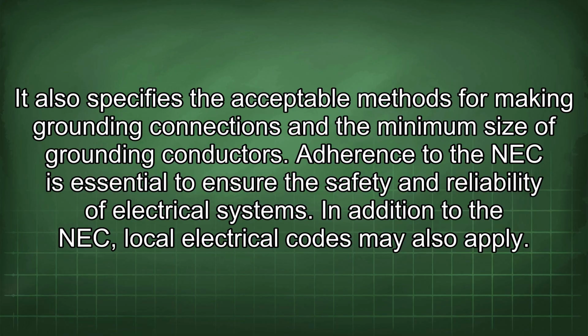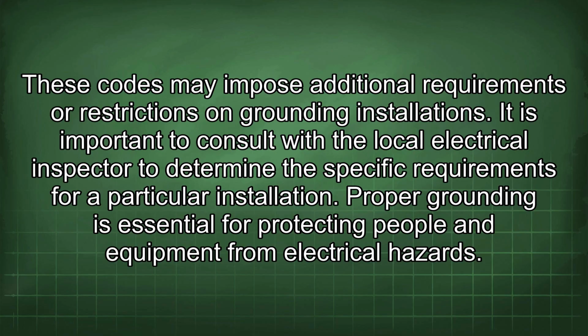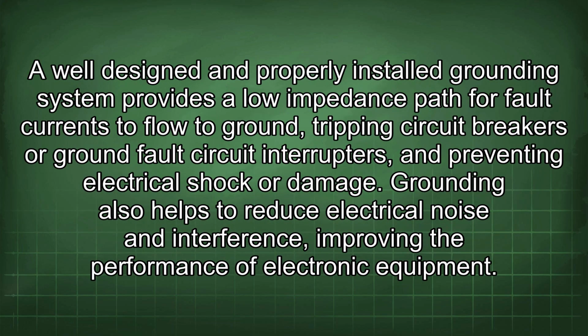In addition to the NEC, local electrical codes may also apply. These codes may impose additional requirements or restrictions on grounding installations. It is important to consult with the local electrical inspector to determine the specific requirements for a particular installation. Proper grounding is essential for protecting people and equipment from electrical hazards. A well-designed and properly installed grounding system provides a low-impedance path for fault currents to flow to ground, tripping circuit breakers or ground fault circuit interrupters, and preventing electrical shock or damage. Grounding also helps to reduce electrical noise and interference, improving the performance of electronic equipment.